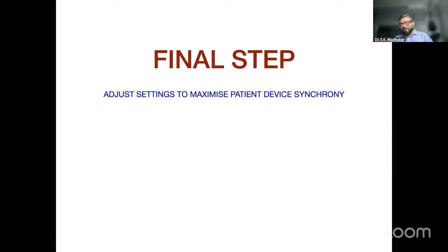What does synchrony mean? Synchrony means the patient's neurogenic inspiratory time and expiratory time is consistent with the machine's mechanical inspiratory time and expiratory time. So when the patient is in inspiration, the ventilator should be in inspiration. When the patient is in expiration, the ventilator should be in expiration. This synchrony should be maintained. And how will you maintain this synchrony is what the final step will be about.